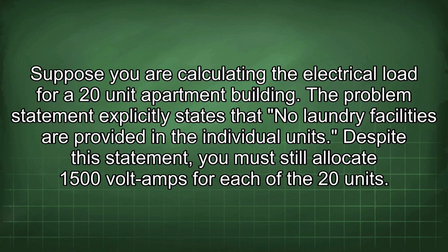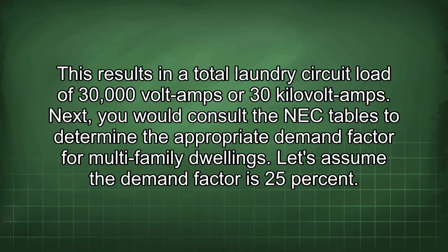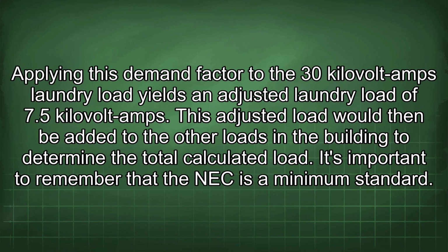Despite this statement, you must still allocate 1500 volt amps for each of the 20 units. This results in a total laundry circuit load of 30,000 volt amps or 30 kilovolt amps. Next, you would consult the NEC tables to determine the appropriate demand factor for multi-family dwellings. Let's assume the demand factor is 25%. Applying this demand factor to the 30 kilovolt amps laundry load yields an adjusted laundry load of 7.5 kilovolt amps. This adjusted load would then be added to the other loads in the building to determine the total calculated load.